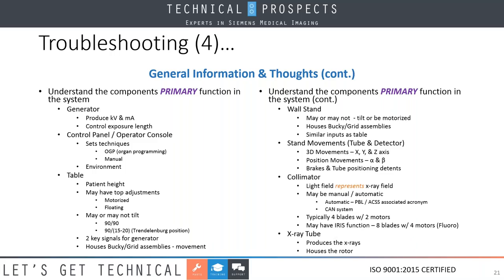The collimator has a light field that represents the X-ray field, all right? And that's important because this is something that you're going to be calibrating. They may be manual collimators or automatic ones. Automatic has a couple of associated terms, one called PBL and the other is ACSS. PBL stands for positive beam limitation. ACSS stands for automatic cassette size and sensing. What this does is it limits the size of the X-ray field to the actual size of the detector or cassette. This is also part of a CAN system. Now, CAN systems is something that we borrowed from the automotive industry to ensure quick communication between various devices and to have our system respond automatically for us.